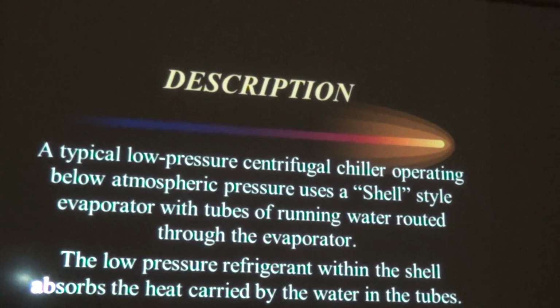But so what we're going to do is we're going to use the air conditioning part of this chiller system to chill the water and to give off the heat that the water absorbs. But the refrigeration cycle is exactly the same as type 1, type 2. That's why type 3 is no big deal to take this part of the test. The only thing you got to know is about two things we're going to talk about that's different. One's going to be the purge system, and the other's going to be ruptured disc.